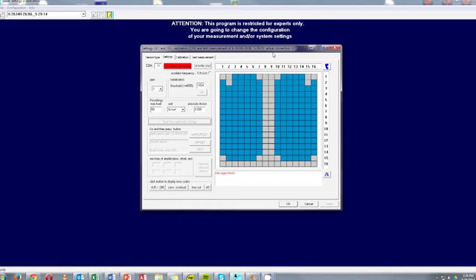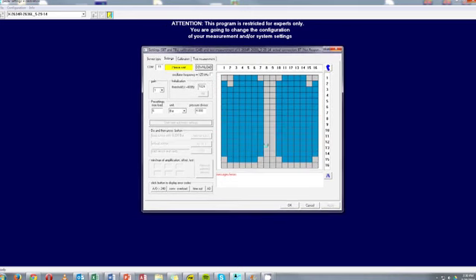After clicking OK, the settings screen appears. Since the manometer provided with the pedar system measures the pressure in bar, we will have to change this in the max load settings from 60 Newton per square centimeter to 6 bar. After changing this setting, click the Download button. This will now download the raw A to D values from the pedar insoles.